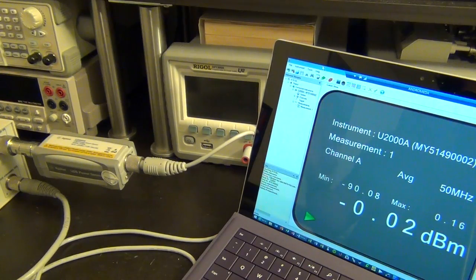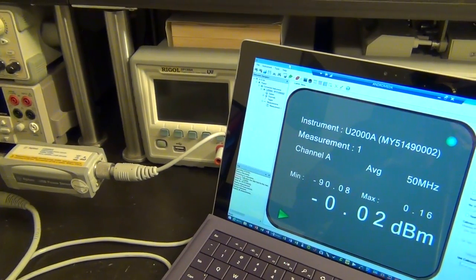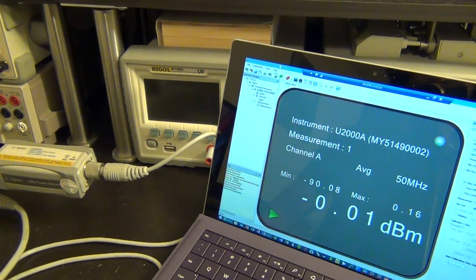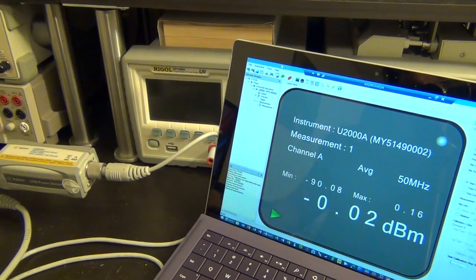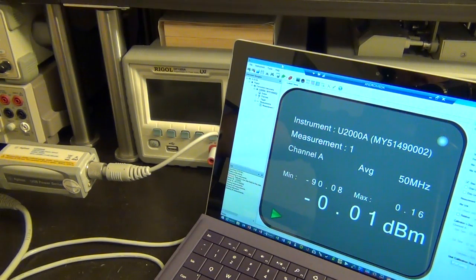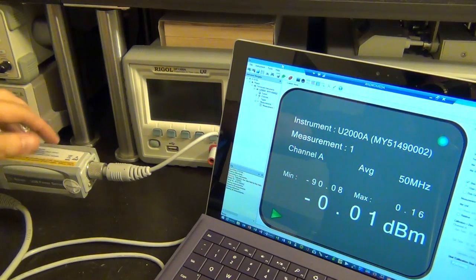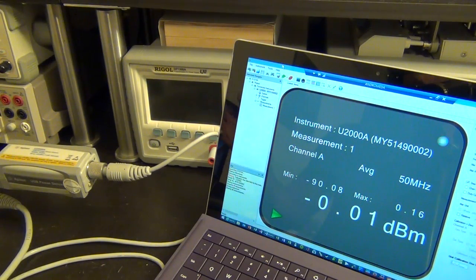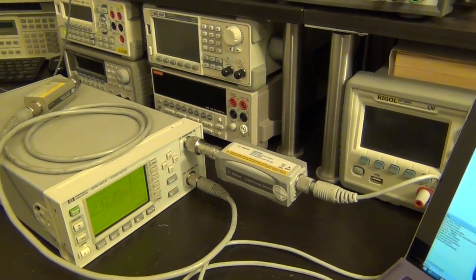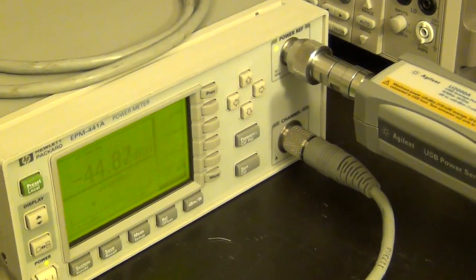And oh, look at that. Oh, it's so close. There it is. So it's reading minus 0.01, which is really close, and it's within the calibration limit of this power sensor that I have. So I would increase the power maybe just a tiny amount, but anyhow, I can always do that later. There's nothing special about it. You saw it was just a potentiometer inside. You just turn the potentiometer and then you can increase the power. So it looks like it is indeed fully functional, and it is working. So another successful repair, I would say.